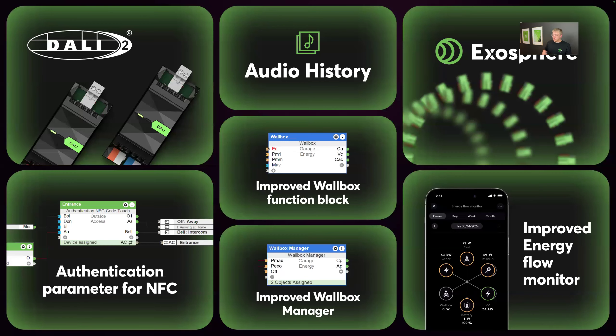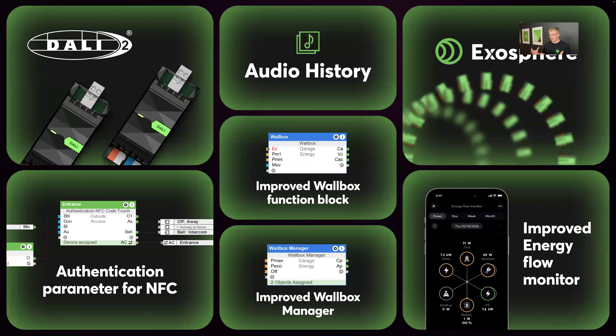The Wallbox Manager ties in naturally with the Wallbox. If, say, 7.4 kW is available for a bank of Wallboxes and one car takes all 7.4 kW, a second car that then plugs in won't get any power because it's already been allocated. The Wallbox Manager now ensures the allowed power is shared and redistributed across all Wallboxes currently in use.